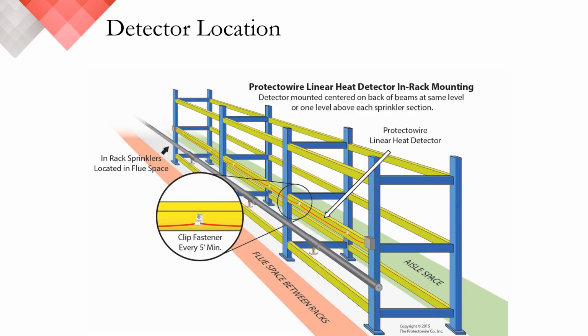To further clarify how Protectowire can be positioned within the racks of a refrigerated or freezer warehouse, here we have an isometric illustration. The Protectowire is installed on the back of the longitudinal load beam and supported every 3 to 5 feet, or approximately 1 to 1.5 meters, using our JD1 J-clip.